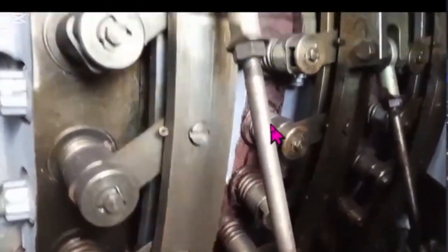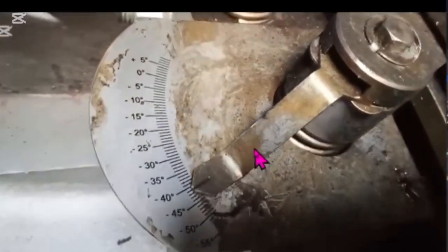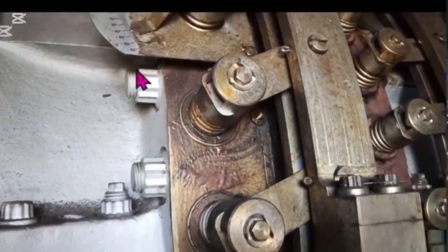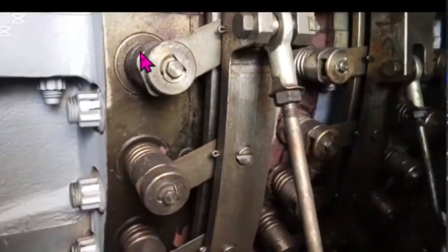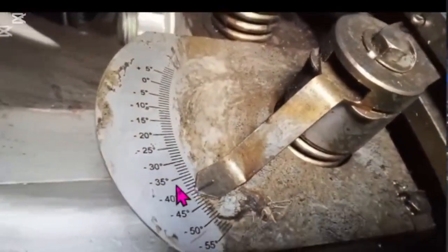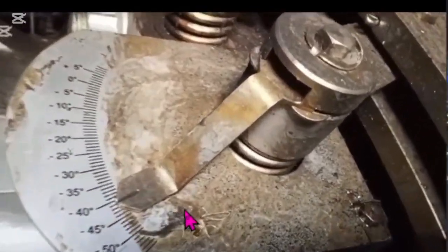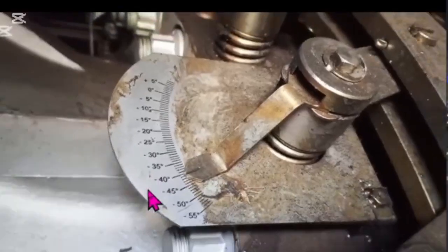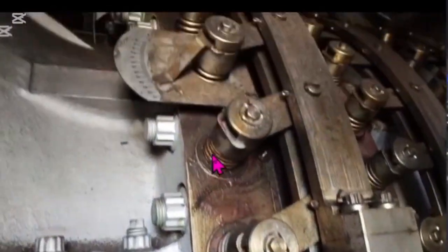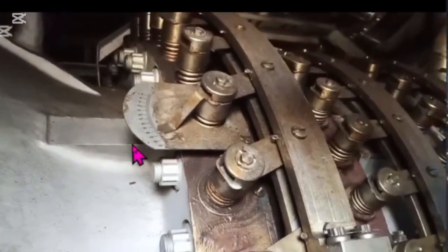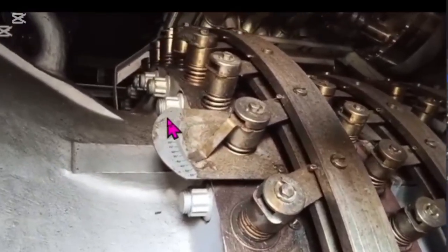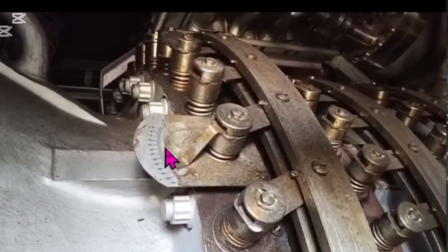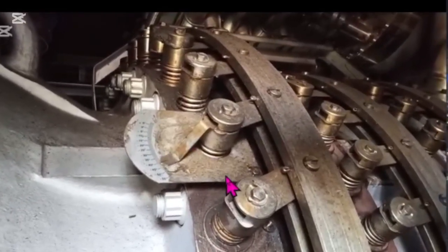Now we'll check in the field by applying the reference value. You see it is rotated. This is the degree. We applied the command and we followed that. It is rotating. You see, here is likely -40, and now we applied the signal value of 50 and we will follow that. It will rotate to its mid value or not.